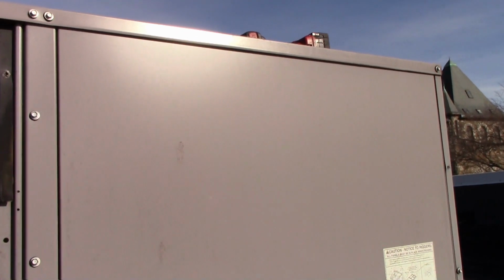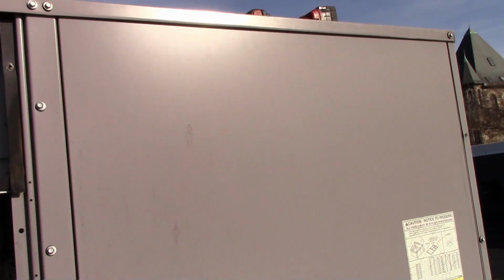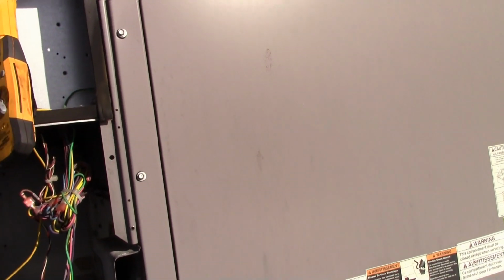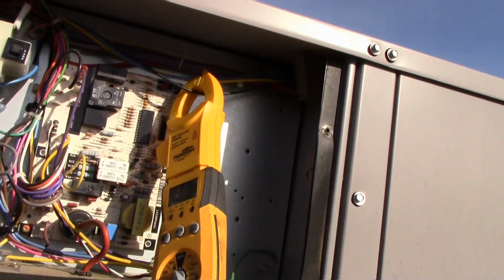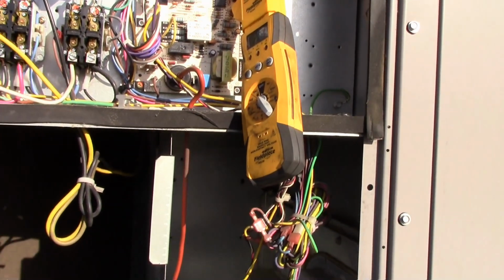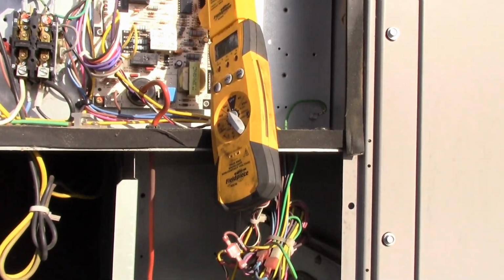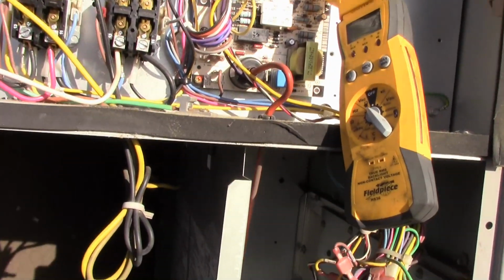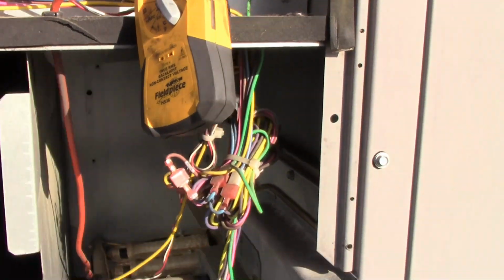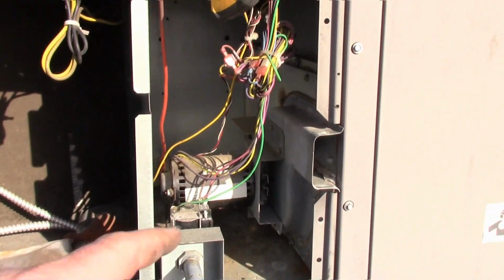Okay, so we're ready to go. When you test an amperage on your motor, put all your panels back on so it's sucking the air from where it should be and you're getting a true amperage reading. Our full load on the motor should be 5.6 to 5.8, somewhere in that neighborhood. Should be good.